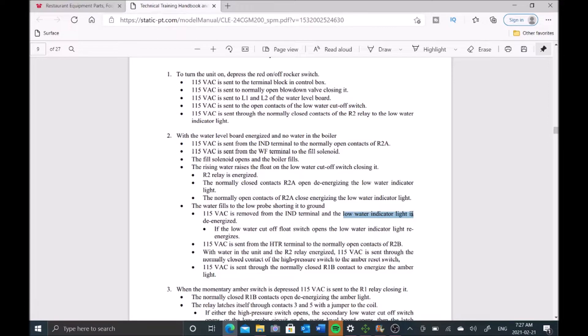So we have double protection - we have the low water probe that removes our low water light, and then we also have our secondary low water cutoff float switch that potentially removes that light, telling the board that we have enough water in the boiler and we can fire up the burner.